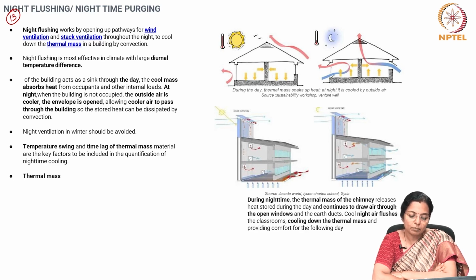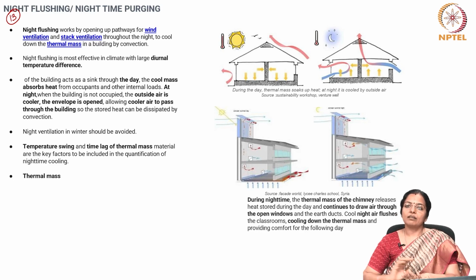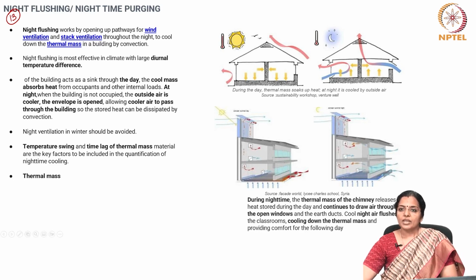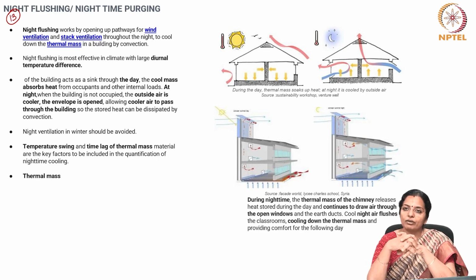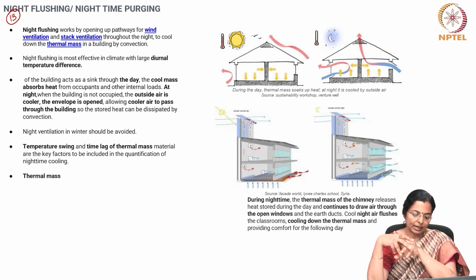At night, when the building is not occupied, the outside air is cooler. The envelope is opened, allowing cooler air to pass through the building so that the stored heat can be dissipated by convection. Night ventilation in winter should be avoided. Temperature swing and time lag of the thermal mass of the material are the key factors to be included in the quantification of nighttime temperature.